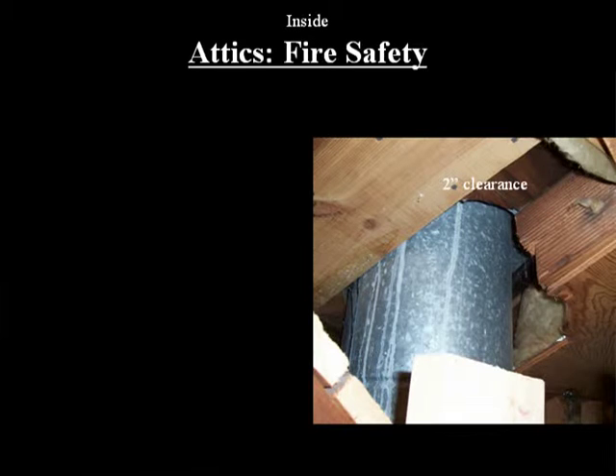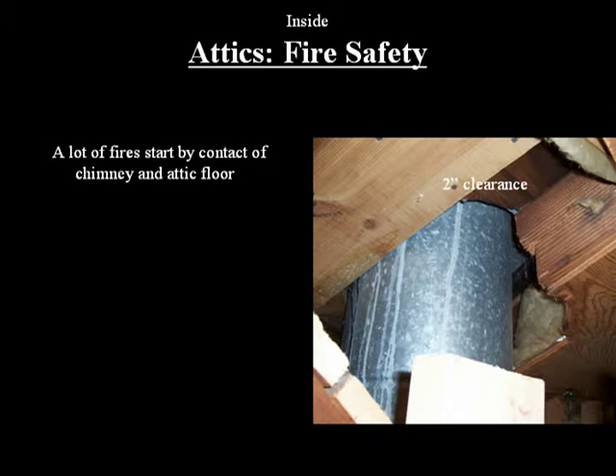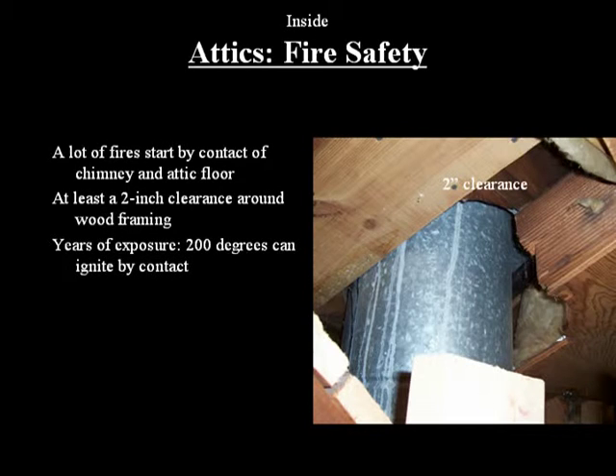Our last topic of discussion in the attic will be fire safety. A lot of house fires have started by the contact of a prefabricated chimney and the attic floor. All building codes have at least a 2-inch clearance around wood framing. Wood normally burns at temperatures around 500 degrees, but years of exposure to lower temperatures around 200 degrees can cause it to ignite by contact.